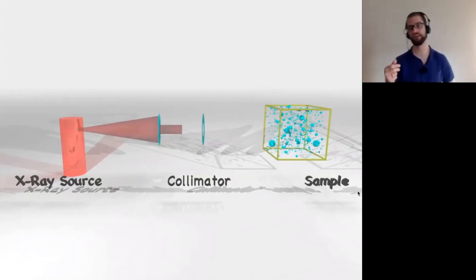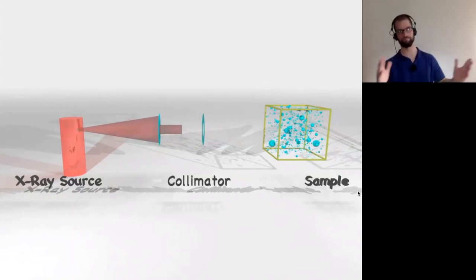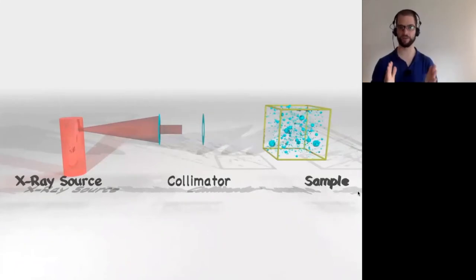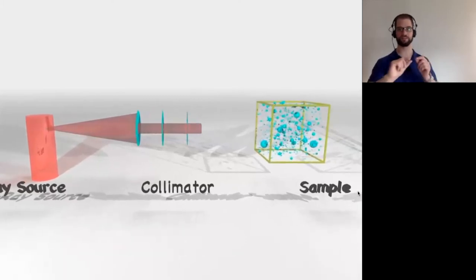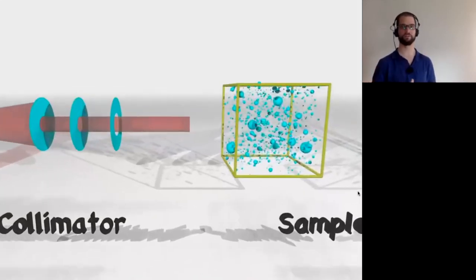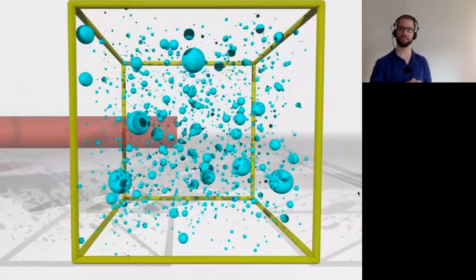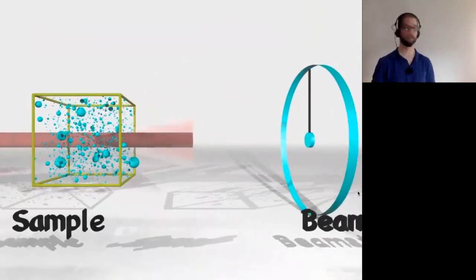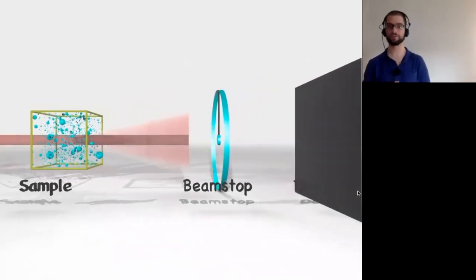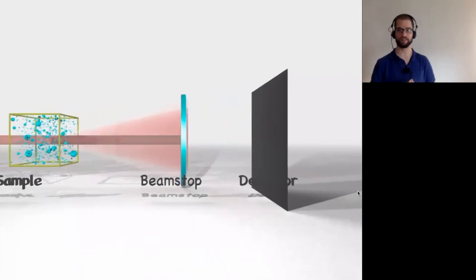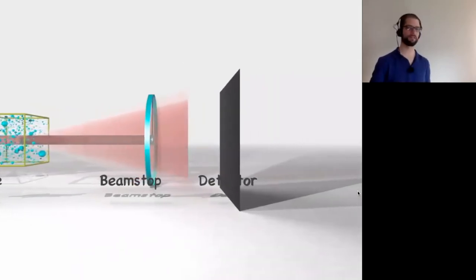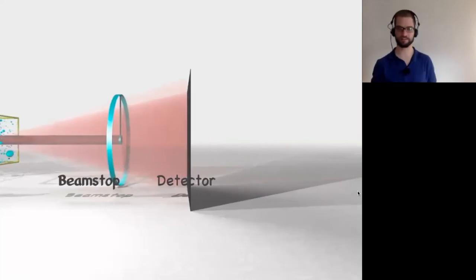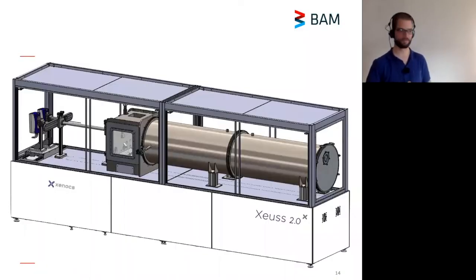Then you cut down these x-rays with a collimator so that you get a nice shaped beam out — in our case about half a millimeter across. Electron density differences in your sample will cause a small fraction of this radiation to be scattered and diffracted. We stop the direct beam with a beam stop to improve our signal and collect the scattered radiation onto our detector. It seems simple in theory, and it is actually also simple in practice.